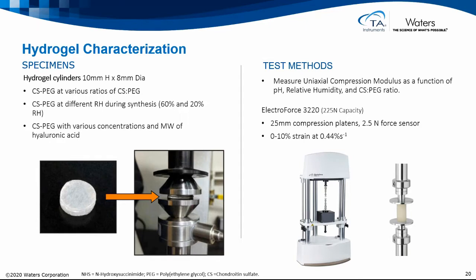An interesting element here is a 2.5 Newton force sensor. So in an instrument like this, which is a 200 Newton capacity instrument, if the material will only yield, say, 1 Newton or less of force during compression, it's helpful to use a lower capacity force sensor. This boosts the signal and gives you more accuracy and resolution in measuring the compression force with more precision.